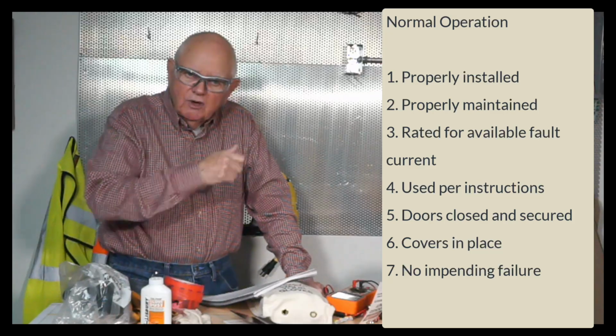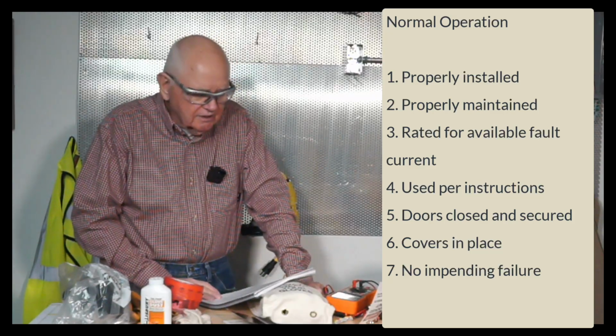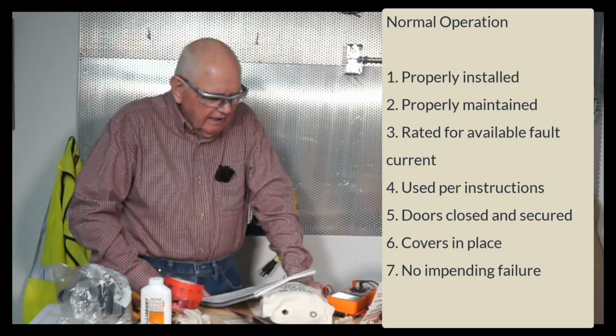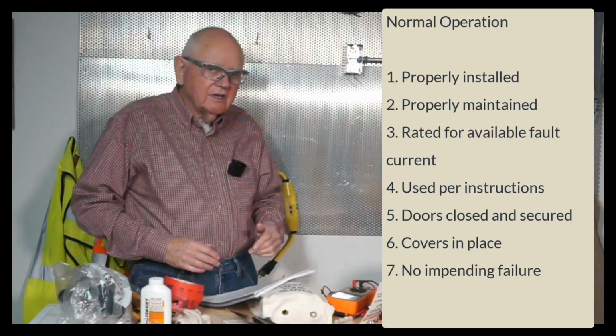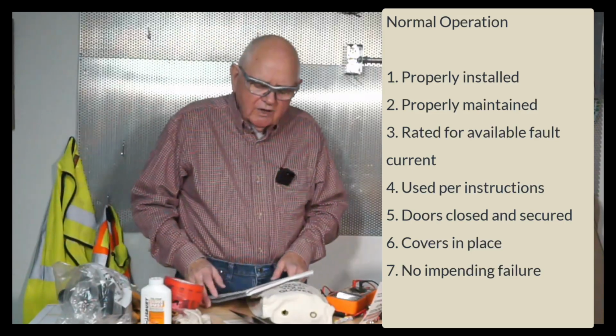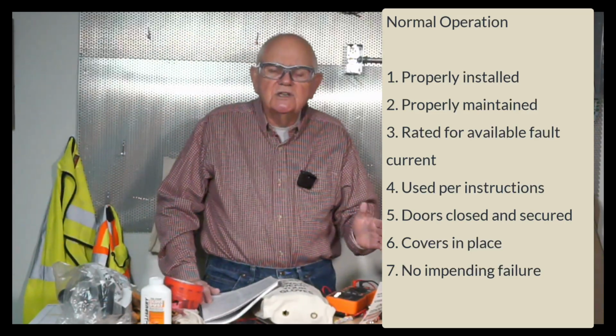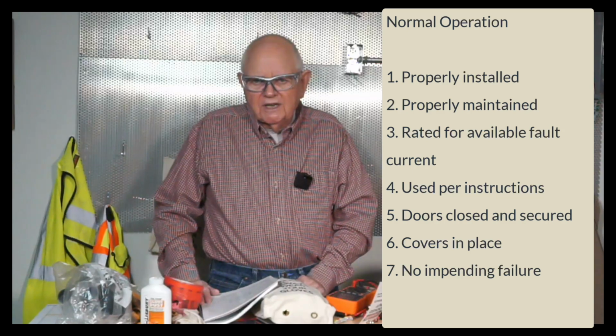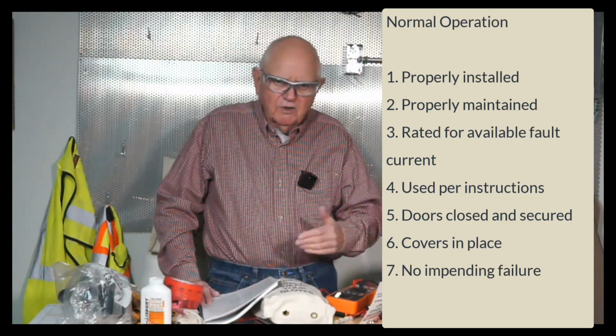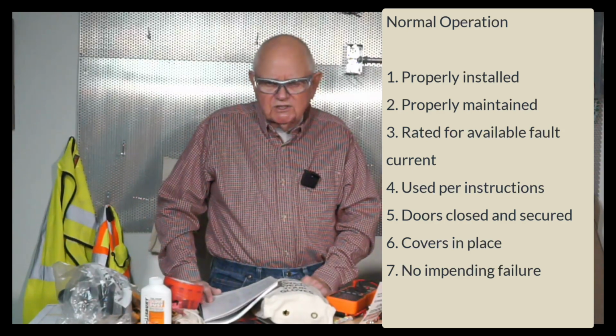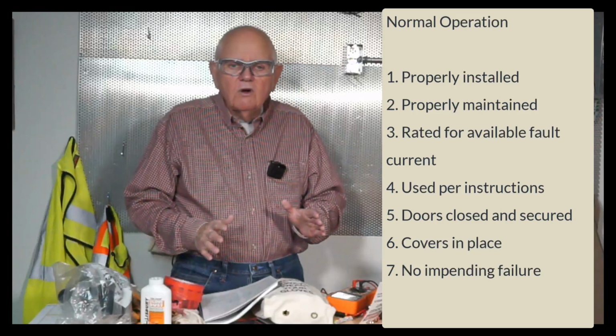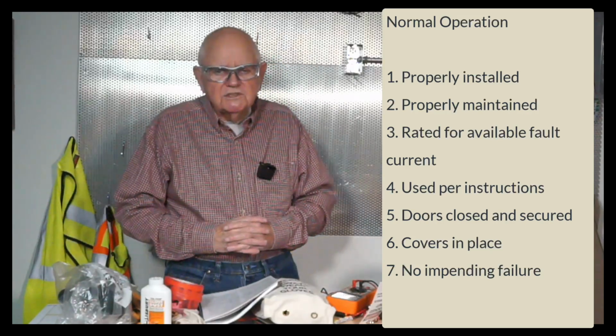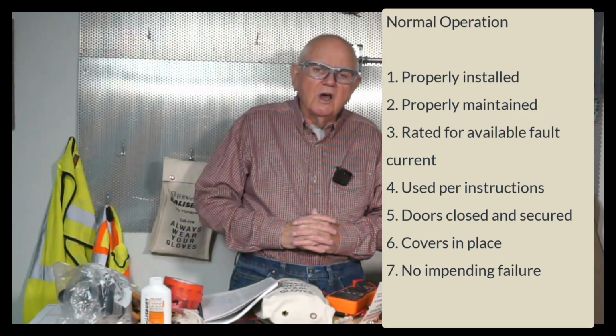That includes all the bolts are in and so on, and proper types of bolts. And there's no evidence, it says, of impending failure. And that's sort of what I call that electrical common sense. No water dripping on the equipment, anything like that. No signs of burn marks, no smell of burnt insulation. If I meet all of those requirements, it says then the equipment's considered suitable for normal operation.